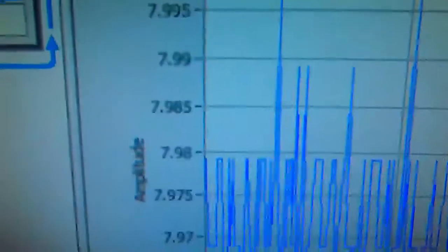Also, if we zoom in on the measurements here, we can see a value of nearly 80%. It's sitting around 7.978. I'm not sure how clear that is on the video. It's hard for me to hold the camera steady enough. So all three things are agreeing, apart from the float measurement, which is actually sitting at nearly 100. So that's just poor calibration of the actual level sensor itself, but the signal calibration is fine. Okay, that's all for now then. I hope that helps with your coursework.